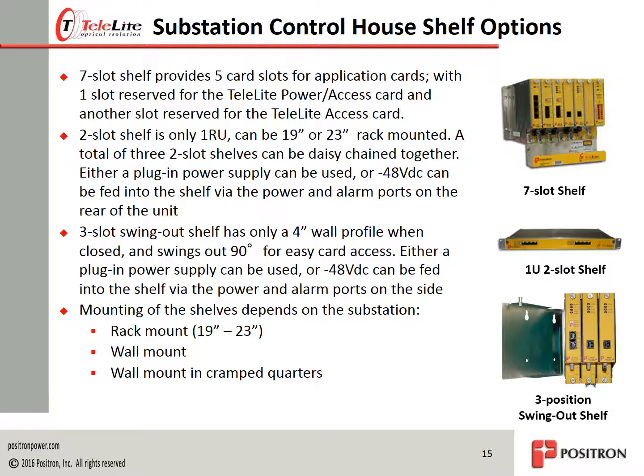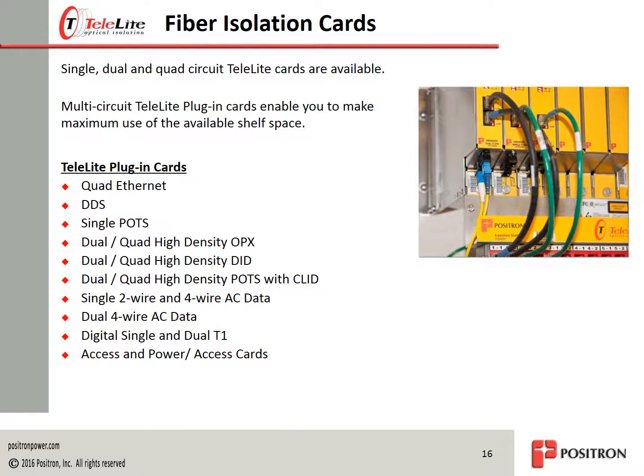When open slots are blanked, the nature of these stainless steel shelves enable them to act as virtual Faraday cages, enabling extreme immunity in the high-noise environment of a power substation. To continue the flow of communications and control circuits using dielectric fiber into the control house, a wide assortment of single, dual, and quad circuit TeleLite cards enable you to achieve a high circuit density using only a single shelf at either end of the fiber span to accommodate any current services delivered by the telephone company.